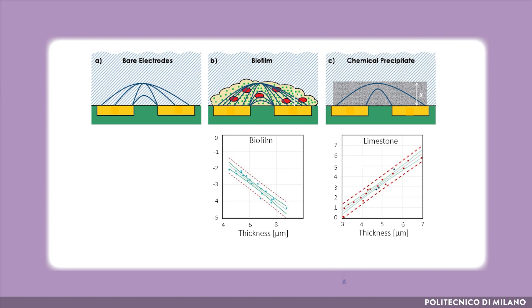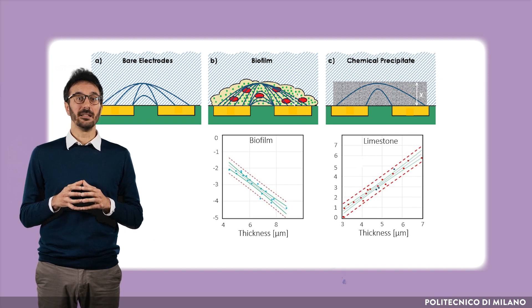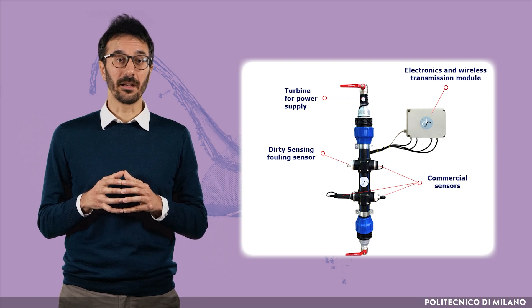More in detail, the formation of a biofilm on the sensor surface results in an increase in the electric field generated from the electrodes, as a consequence of the increase in conductivity determined by the high ionic concentration in the biofilm. On the contrary, inorganic deposits determine a decrease in the electrical field, as the precipitated solid matrix limits the conductivity. In both cases, for inorganic and organic fouling, the electrical response is proportional to the slime thickness. Therefore, Dirty Sensing is an accurate and selective instrument for the real-time and low-cost measurement of fouling.